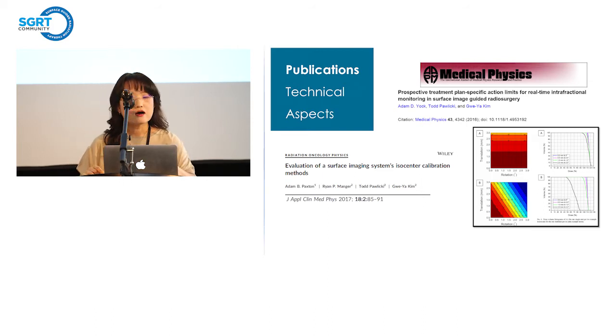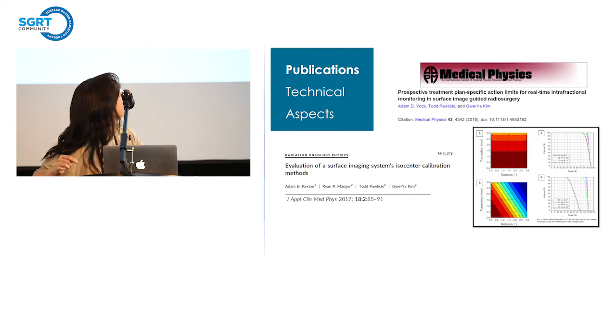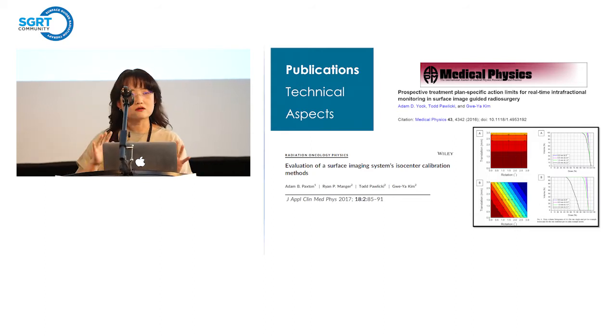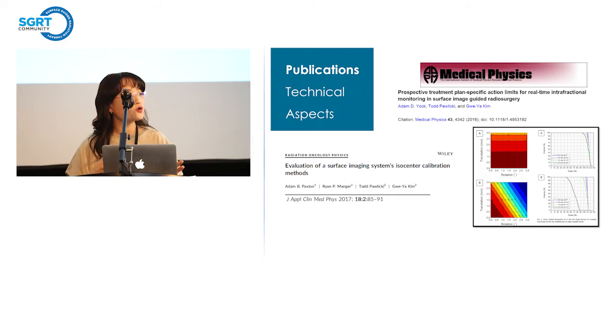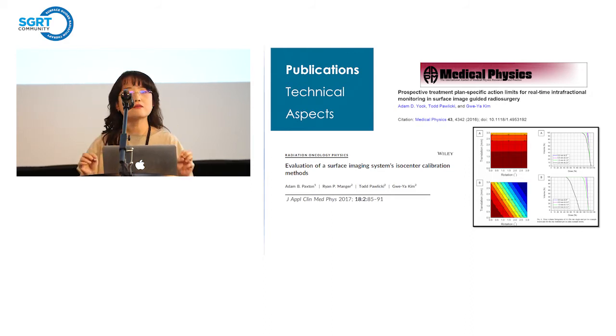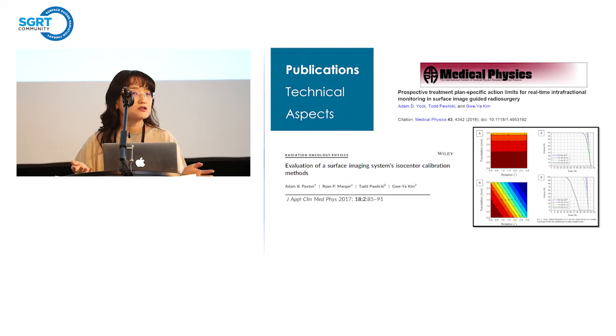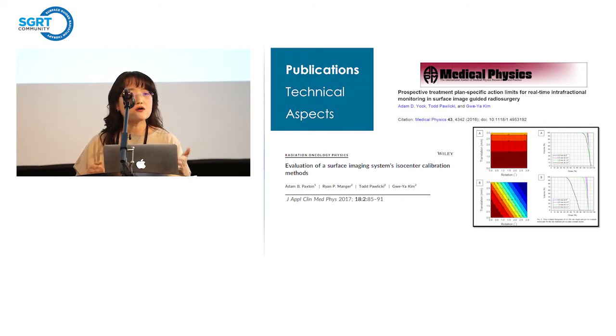And then there is another publication, a prospective action limit design per patient plan. So think about your metastatic cases. You have off-axis targets everywhere, and you use the same tolerance to stop the beam and then reposition or correct some issue. It depends on how far off-axis the metastasis is from your isocenter. You can design those tolerances to stop the beam to achieve your coverage. So this is the publication in Medical Physics.